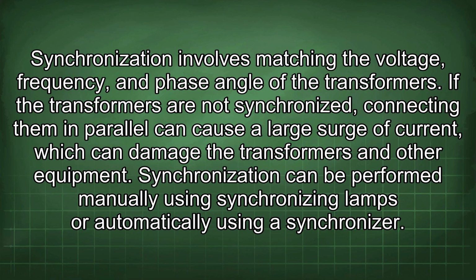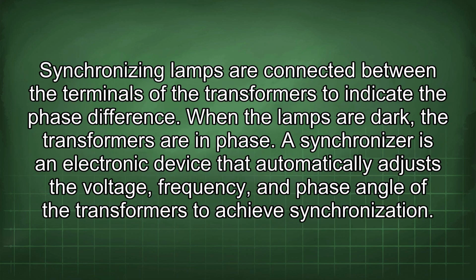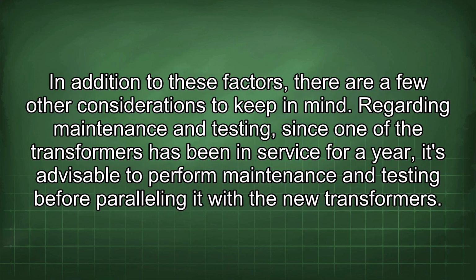Synchronization can be performed manually using synchronizing lamps or automatically using a synchronizer. Synchronizing lamps are connected between the terminals of the transformers to indicate the phase difference. When the lamps are dark, the transformers are in phase. A synchronizer is an electronic device that automatically adjusts the voltage, frequency, and phase angle of the transformers to achieve synchronization. In addition to these factors, there are a few other considerations to keep in mind.